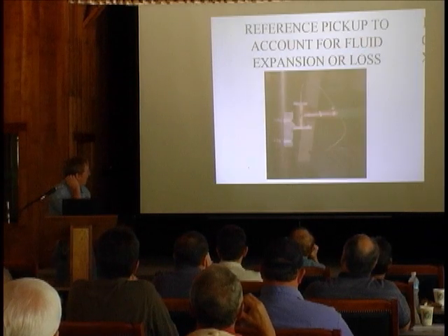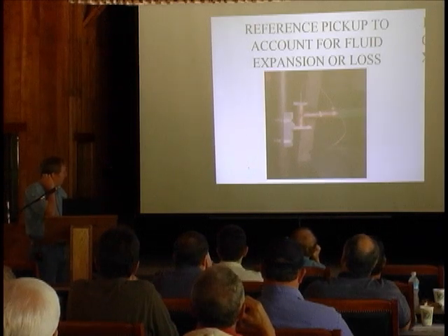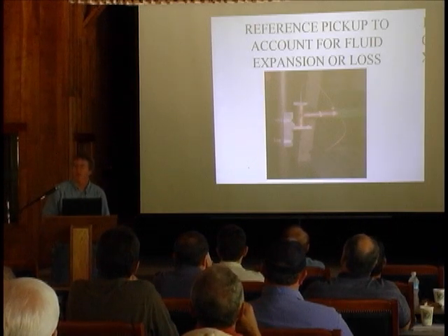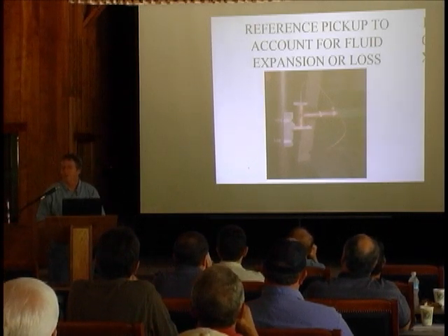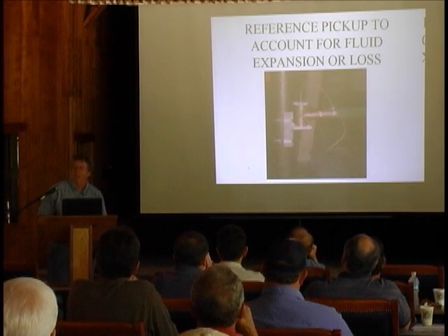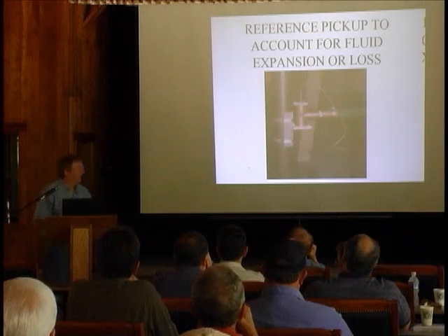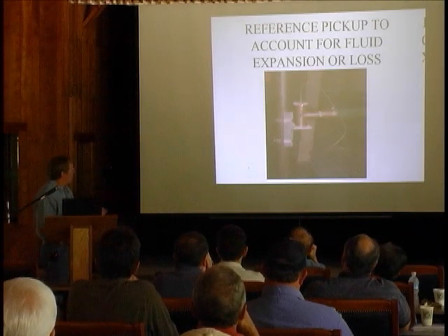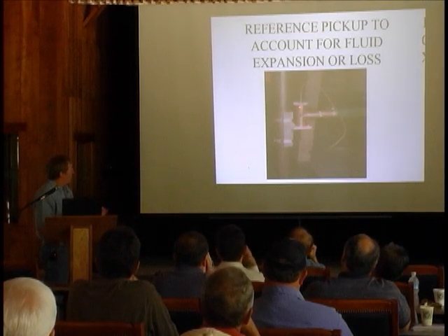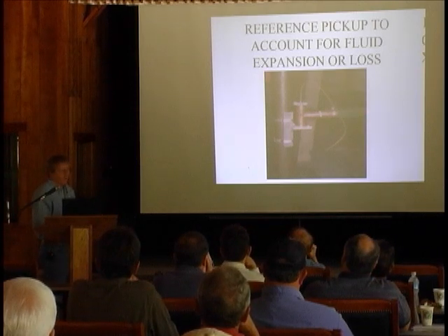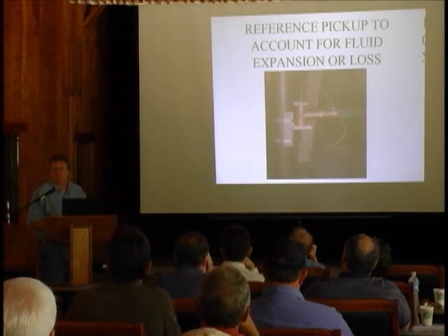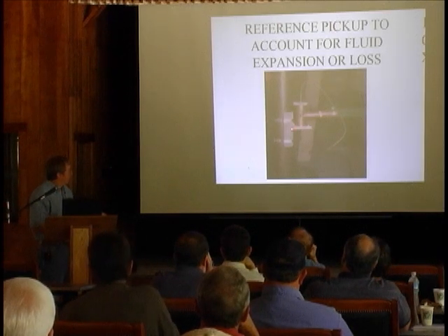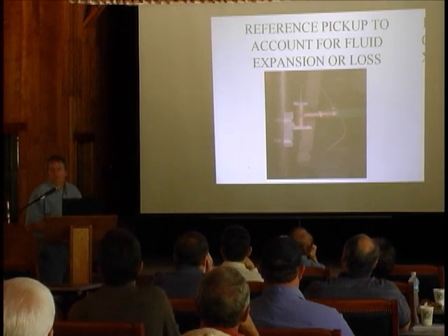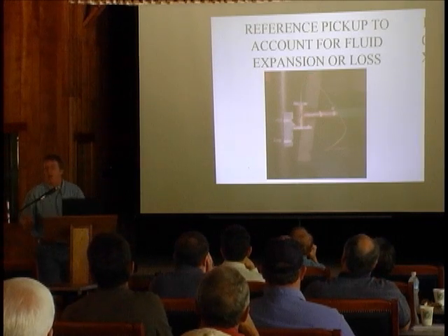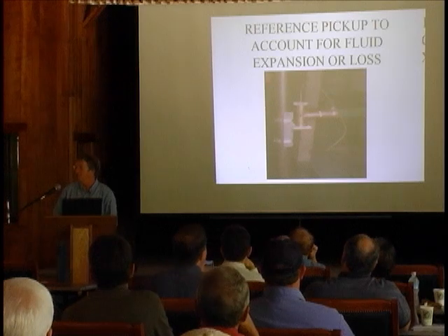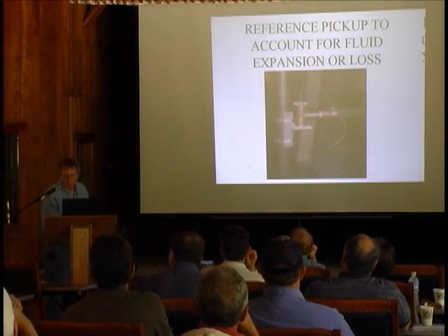So what I did, I modified the Canadian design, because I said, well, yeah, but what if the glycol heats up? That's going to swell it up, and how are you going to tell? What if I get a leak or anything like that? So I put another probe outside and used that as a reference probe, so anything common to the system, like heating up glycol or leaks, would affect this probe the same as it did the other. Then I just subtracted this probe from the other, and all I would ever get is any change due to that probe alone.